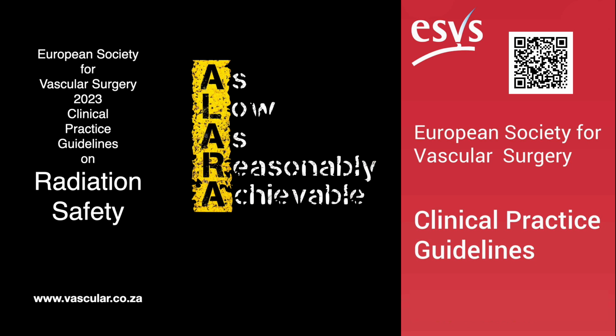What else? There are also suspended personal radiation protection systems. These are more complex setups, often hanging from a ceiling track. Like the zero-gravity system you sometimes hear about. That's one well-known example, yes. These systems can provide much more comprehensive whole-body shielding than a standard apron, often including integrated face and head protection. They can significantly reduce the operator's dose, especially to the head, neck, and upper body, compared to traditional PPE. The guidelines suggest they may be considered, particularly in high-volume or high-dose environments where minimizing operator dose is a major priority. Like a personal radiation force field, almost. A bit like that, yes. They take the weight off the operator, too, which is a bonus.